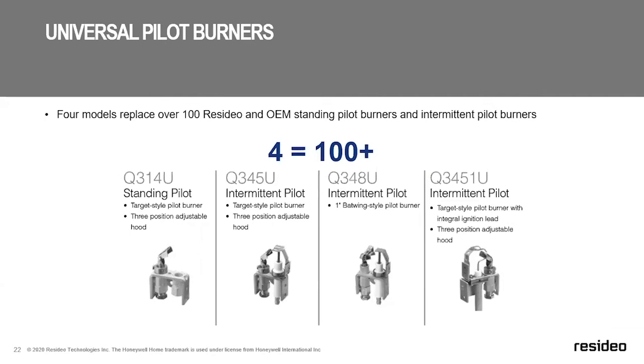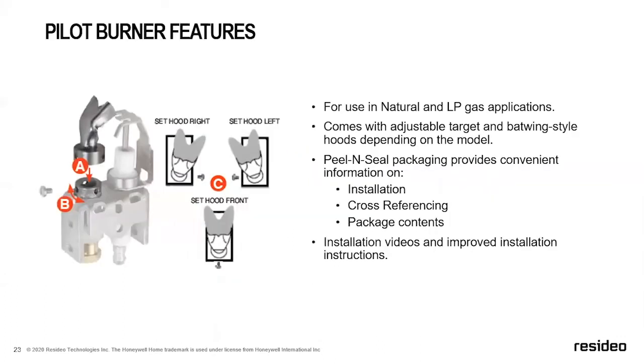The standing pilot model alone replaces approximately 35 or 40 models that you see out in the field. For the other 3, depending on the type of hood that you have, whether it's a batwing or a standard target style, or whether you need an integral ignition lead, that's where you would pick which one of these would fit. Here's what makes them different and unique. Well, it's the flexibility of the installation. First of all, the hoods are adjustable. They come set out of the box as a center front hood, but by removing a set screw, you can lift up the hood and move it to the left or to the right, and then put the screw back in, and adjust it as either a right facing or a left facing hood.